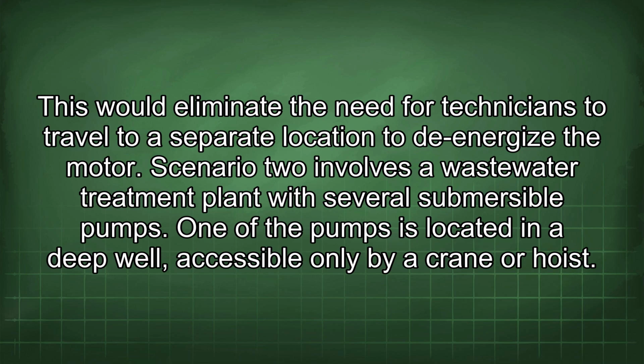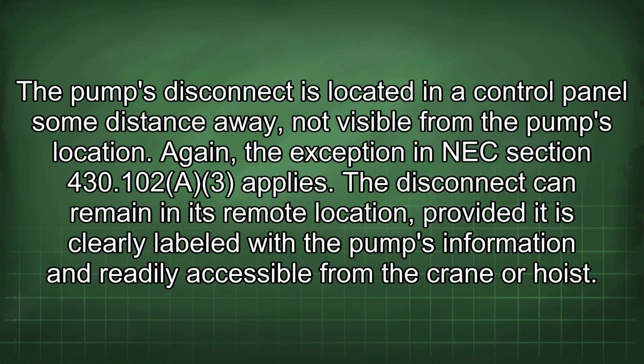Scenario 2 involves a wastewater treatment plant with several submersible pumps. One of the pumps is located in a deep well, accessible only by a crane or hoist. The pump's disconnect is located in a control panel some distance away, not visible from the pump's location. Again, the exception in NEC Section 430.102 A3 applies. The disconnect can remain in its remote location, provided it is clearly labeled with the pump's information and readily accessible from the crane or hoist.